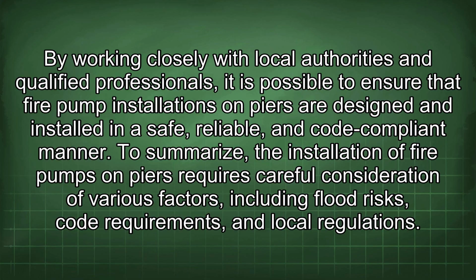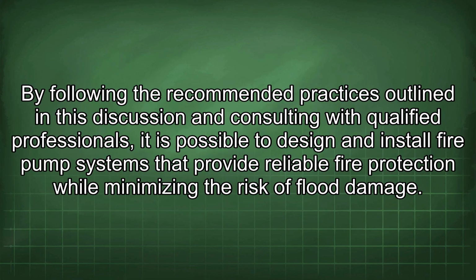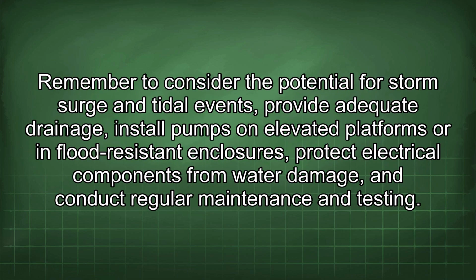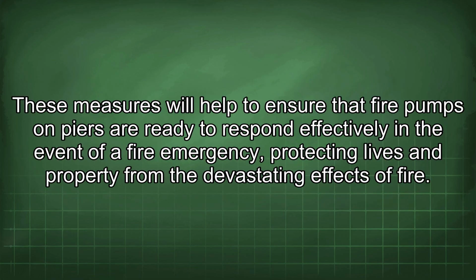To summarize, the installation of fire pumps on piers requires careful consideration of various factors, including flood risks, code requirements, and local regulations. By following the recommended practices outlined in this discussion and consulting with qualified professionals, it is possible to design and install fire pump systems that provide reliable fire protection while minimizing the risk of flood damage. Remember to consider the potential for storm surge and tidal events, provide adequate drainage, install pumps on elevated platforms or in flood-resistant enclosures, protect electrical components from water damage, and conduct regular maintenance and testing. These measures will help to ensure that fire pumps on piers are ready to respond effectively in the event of a fire emergency, protecting lives and property from the devastating effects of fire.